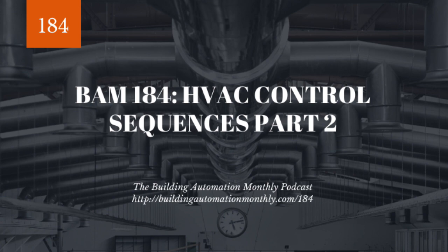And a fan coil also, and I hesitate to say this because it's not always true, but most fan coils will just utilize plenum air for themselves and won't be using outside air. Now, I know as soon as I say that, I'm going to start getting messages from folks saying, well, I've got a fan coil that uses outside air. And you're absolutely right. There are fan coils that use outside air.